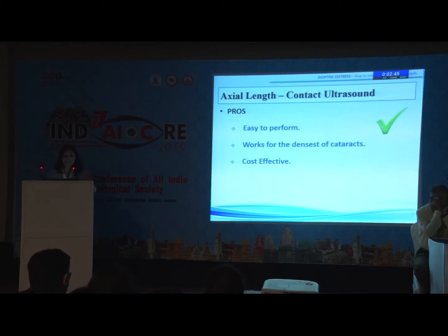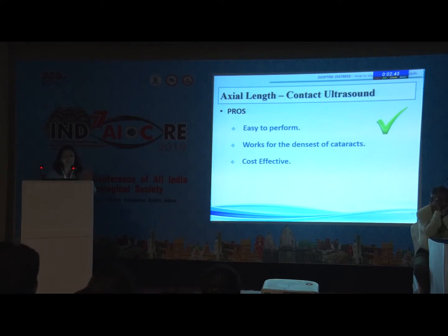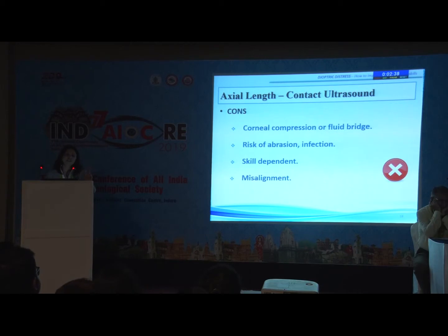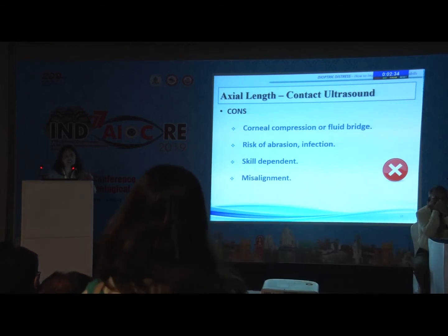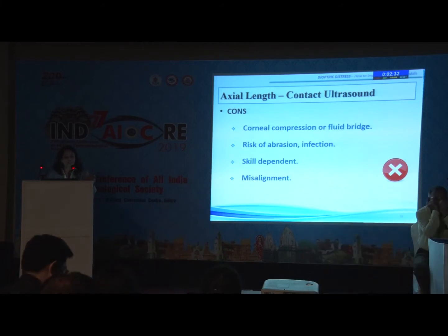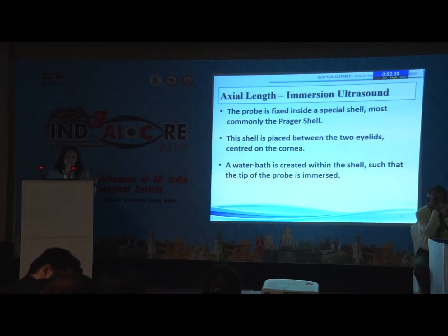Although contact methods are easy to perform and work for dense cataracts and are cost-effective, there is a risk of corneal compression, leading to false measurements. Risk of abrasion and infection is always there, and misalignment issues can occur.